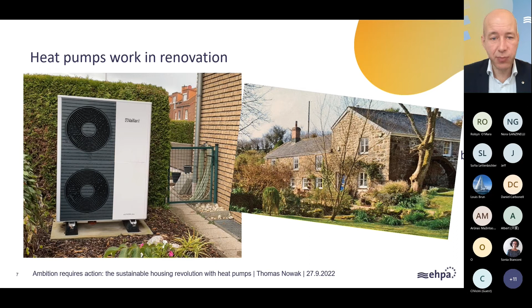Heat pumps work in renovation. Sometimes you have to renovate, where you have to do more for the building envelope, sometimes you don't. The master number is 55 degrees centigrade. If your building can run at 55 degrees centigrade, it's in principle ready for immediate heat pump replacement.